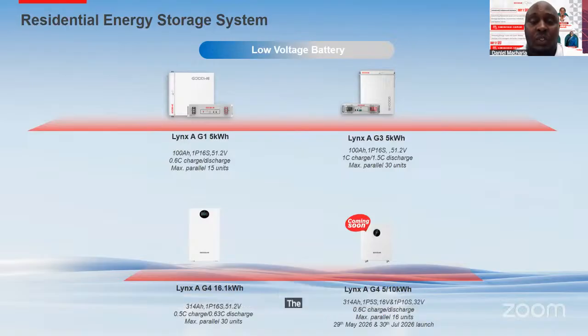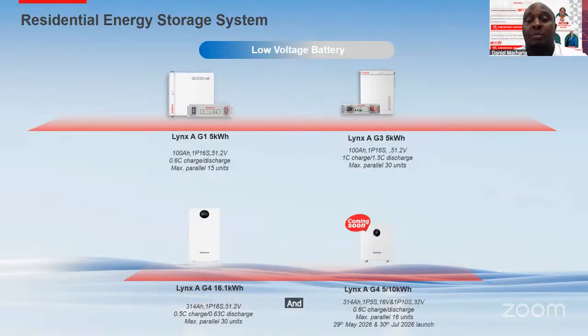For this one, you have the option of having the aerosol for fire protection. It's an optional feature that you can opt to have supplied with the battery. And now we have the inbuilt DC breaker, whereby in case of anything, the breaker inbuilt in the battery can trip and isolate the system.